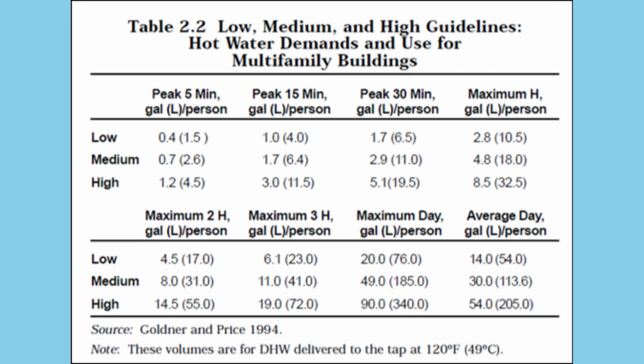What are the MEP engineer's responsibilities? 1. Estimate occupancy. 2. Use ASHRAE daily usage per person. 3. HPWH required recovery, daily usage, desired run hours. 4. Must account for defrost if the HP is air source type. 5. Rule of thumb for storage: 20% of daily usage, based off 16 daily run hours.